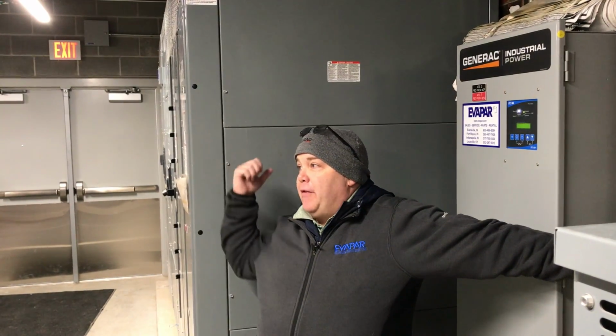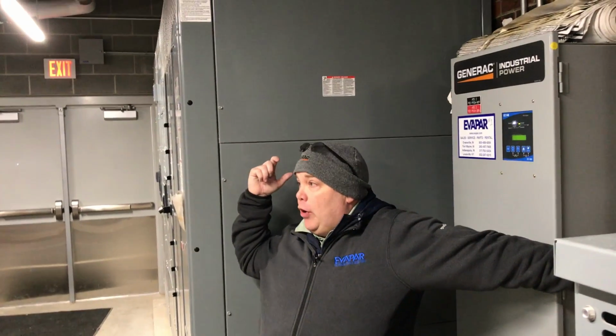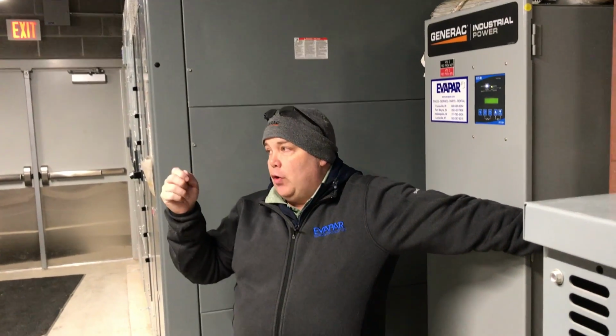That's why you're having that alarm, and that's why you have to go out there, because to clear it out there, you have to turn the unit off, back to automatic, and it clears the alarm. So with a power failure and the generator running, the generator's not sending power to the battery charger. Correct, it's coming from the alternator, the engine alternator. It's charging the batteries while it's running.